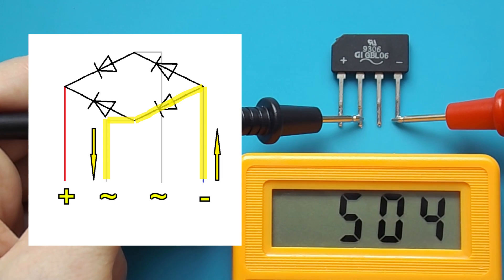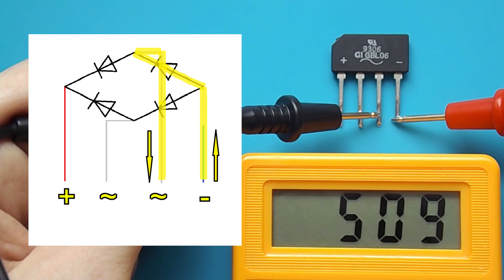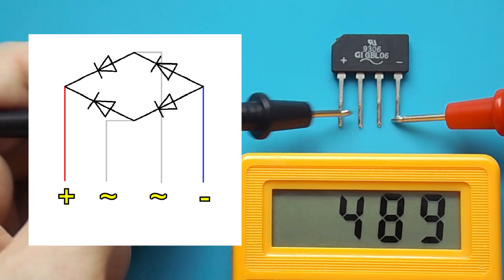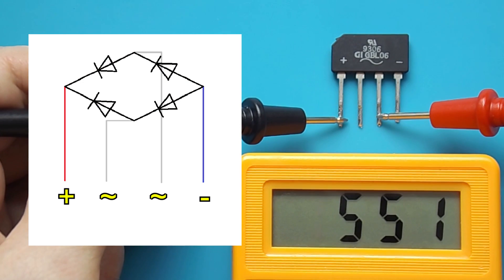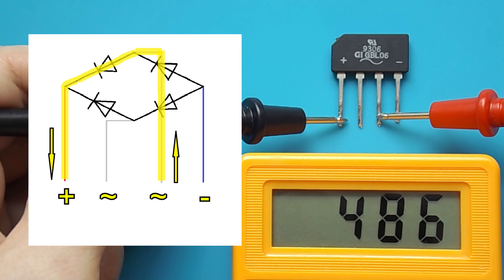Then I check both pins of the AC input for negative. On each leg, the multimeter should show the voltage drop of one diode. Then I repeat the operation in the same way, checking the AC input with respect to the plus.